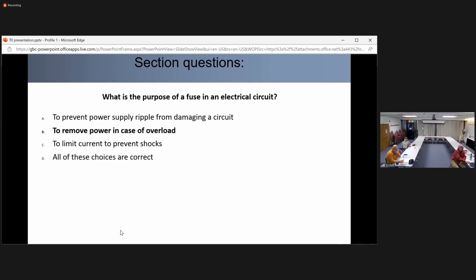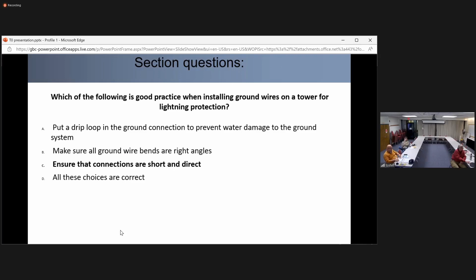So what's a good practice when installing ground wires on your tower for lightning protection? You put a drip loop in the ground connection so water doesn't damage the ground system. You make sure all those wires are nice, neat, right angle bends. Or do you ensure that all the connections are short and direct? Well, B and C are exclusive, so they can't all be correct. The right thing to do is make sure all the connections are short and direct. Energy from lightning doesn't like to make rapid turns, it wants to go in a straight line.